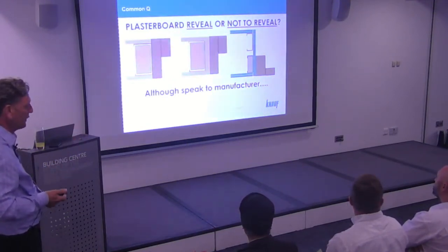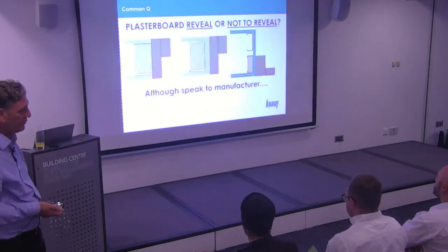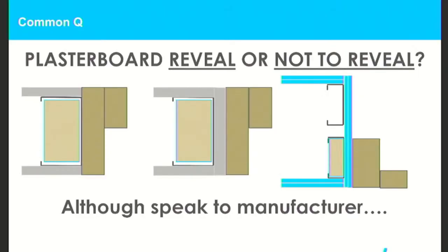However, we're moving towards recommending now in all our specifications that the door jambs are lined, because if you take a 146 stud, put two layers of plasterboard, you end up at 208, and then someone comes and puts a slim door in it, you've got exposed metal to deal with. We're actually leaving the option there for the designer to say we want the door either cloaked or not cloaked.